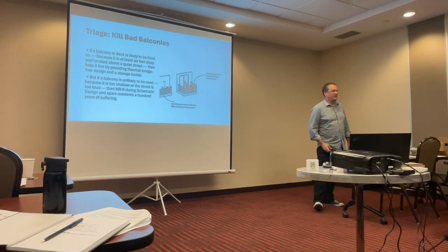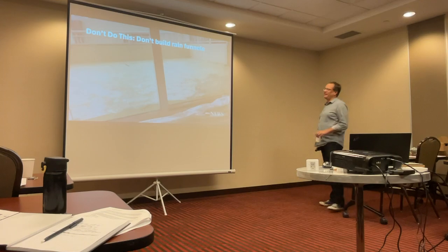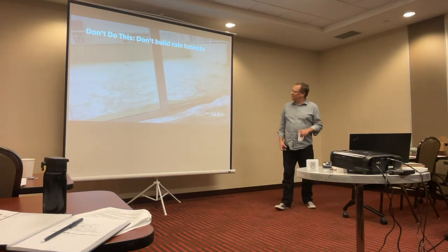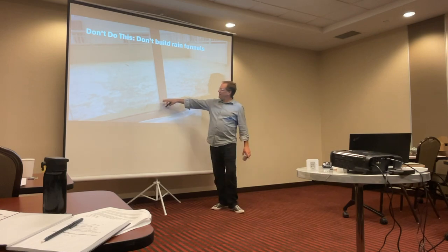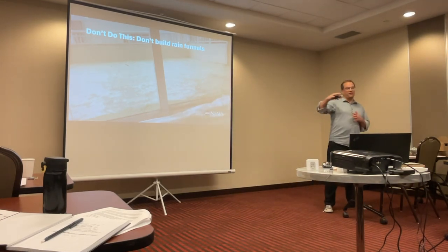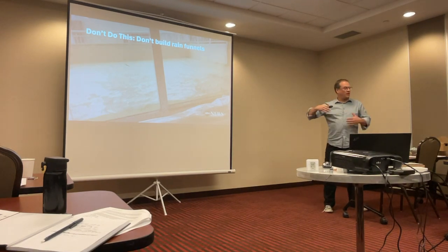Well, I'm also going to advise against VRF, period. Things like climate change. We'll come back to that. Also, don't do this. This is an actual picture of one of our recent Florida storms. Notice the water's on here. It's just the balcony, because it didn't have a lot of drains, only partly overhang, in an intense storm, became a funnel. It's funneling water into the apartment.